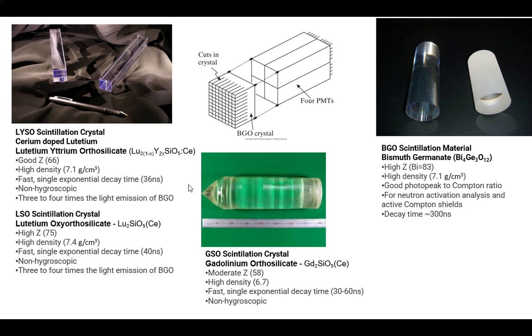The doping you can see here between it, that's not truly doping, it's actually a chemical, right? You've got the option that yttrium and lutetium can actually be used equivalent to each other. So when you make these, you adjust how much of each, see the 1 minus X and the X. Think of that as just alphas. How much do you have of the yttrium versus the lutetium? So you're just adjusting a ratio of those two. And then you're doping it with cerium.